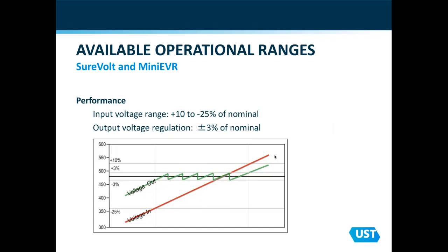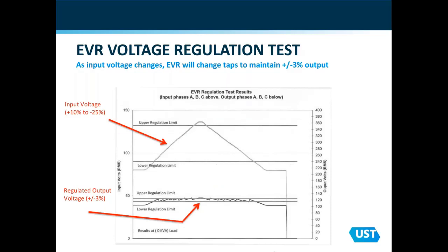This just is a representation of the way the unit operates, and you can see with the red line, as the incoming voltage changes, we are changing taps with the green line in order to maintain a plus or minus 3% output. Same representation, only this is an actual test sheet. You can see the upper chart is us varying the voltage with our variac and increasing the voltage and then decreasing the voltage. And on the bottom chart, we're watching to make sure the taps are changing to ensure plus or minus 3% output.